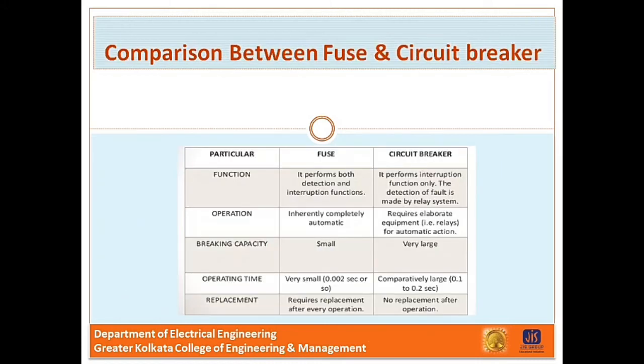Next, comparison between fuse and circuit breaker. First is function. According to function, the fuse performs both detection and interruption of the fault. Now the fuse is an independent equipment that detects the fault and interrupts the circuit, but the circuit breaker only performs the interruption function. The detection of the fault is made by the relay system, and after detecting the fault, the relay initiates the operation of the circuit breaker, and then the circuit breaker operates and disconnects the faulty section from the healthy portion.